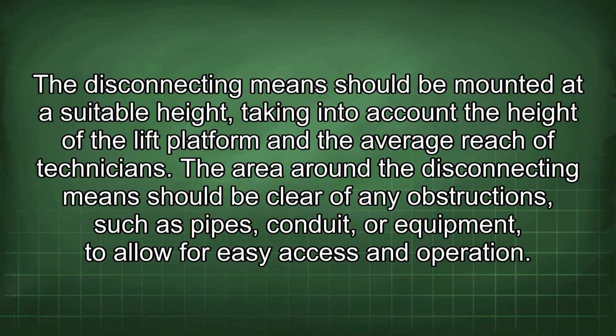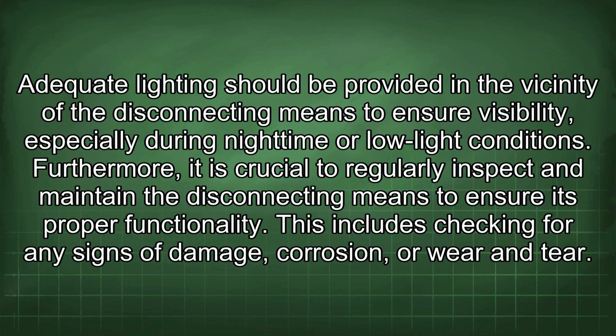The area around the disconnecting means should be clear of any obstructions such as pipes, conduit, or equipment to allow for easy access and operation. Adequate lighting should be provided in the vicinity of the disconnecting means to ensure visibility, especially during nighttime or low light conditions. Furthermore, it is crucial to regularly inspect and maintain the disconnecting means to ensure its proper functionality.